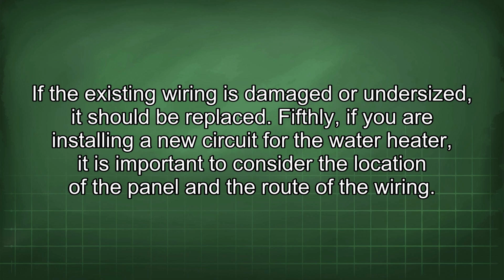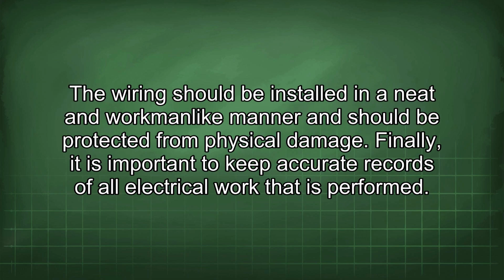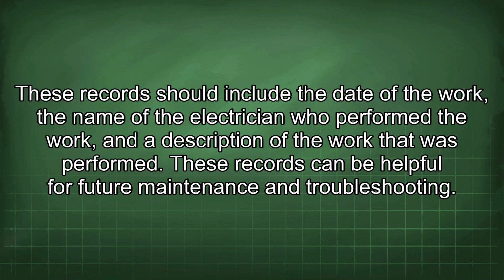Fifthly, if you are installing a new circuit for the water heater, it is important to consider the location of the panel and the route of the wiring. The wiring should be installed in a neat and workmanlike manner and should be protected from physical damage. Finally, it is important to keep accurate records of all electrical work that is performed. These records should include the date of the work, the name of the electrician who performed the work, and a description of the work that was performed. These records can be helpful for future maintenance and troubleshooting.